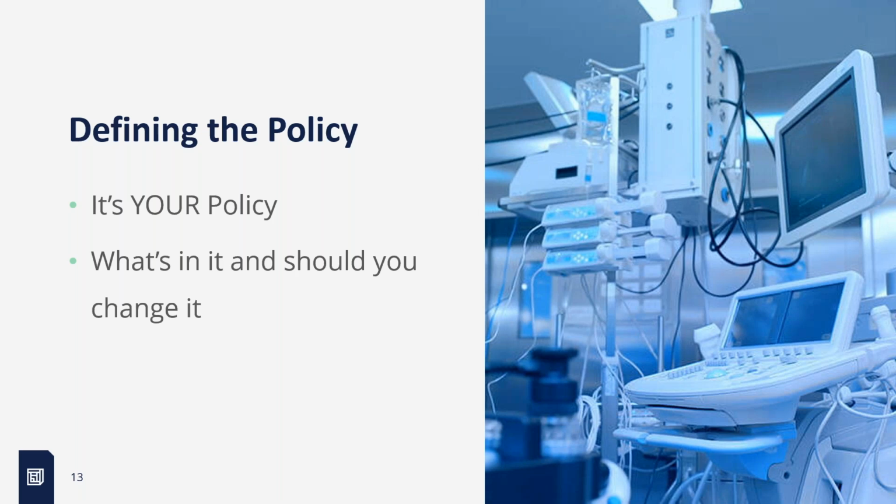Before you move on, help us: ITM, what's that? ITM is a PM. It's an acronym that's being used a little more prevalently on our side of things, maybe on the solutions partner side. It stands for inspection, testing, and maintenance.